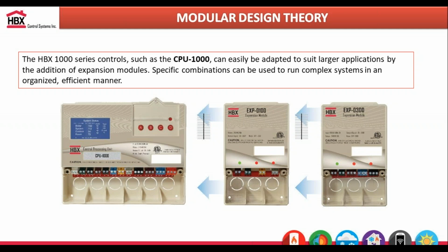So it took us about 2 years from the company founded to actually put out our first controller. The whole basis of the CPU1000 series, as well as our Eco1000 series for the geothermal applications, is all built off modular expandability. The main unit itself can do up to 2 stages. If you need to do more than 2 boilers, you just add on expansion modules to that 1000 just to give you additional relay contacts.